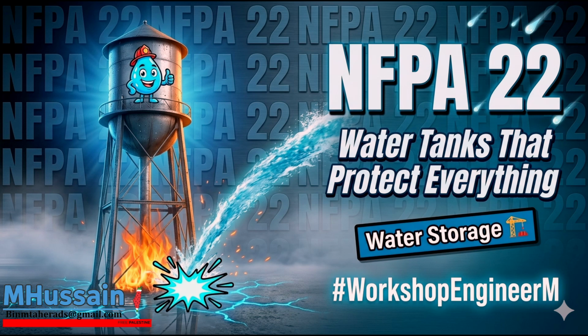How so? Well, according to Gay-Lussac's law, the pressure of a gas is directly proportional to its absolute temperature. Temperature fluctuation. Right. If you pressurize the tank on a hot afternoon and the mechanical room temperature drops 15 degrees overnight, the pressure in the tank will drop simply due to the air cooling and contracting. So an engineer or inspector who doesn't account for temperature differentials might fail a perfectly sealed tank. Or worse, pass a leaking tank if the room heated up and masked the pressure loss. Thermodynamics impacting hydrostatic testing. That is exactly the level of detail safety engineers need to consider.